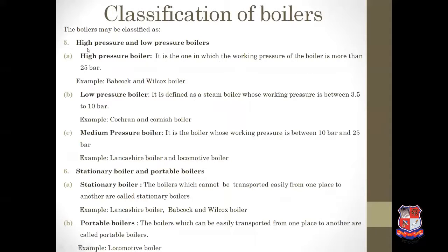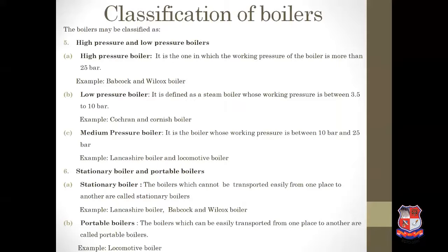Next classification is high pressure and low pressure boiler. If the working pressure of the boiler is more than 25 bar, it is called a high pressure boiler — example is the Babcock-Wilcox boiler. If the working pressure is between 3.5 to 10 bar, it is called a low pressure boiler — examples are Cochran and Cornish boiler. If the working pressure is between 10 bar and 25 bar, it is called a medium pressure boiler — examples are Lancashire boiler and locomotive boiler.